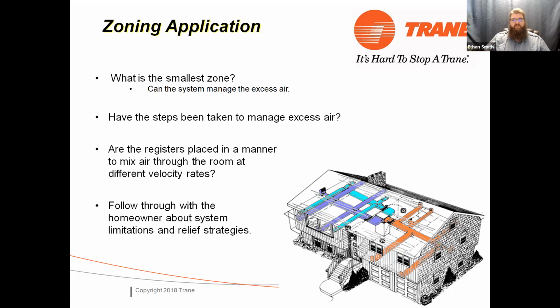I have a customer that I've been working with, a contractor, for upwards of 2 years, that thinks that because she sets her master bedroom to 65 degrees, she can then set her living room, which shares a wall with the master bedroom, to 75 degrees and have them be at set point all the time. Okay. Is that a realistic expectation out of a zoning system? No, not really. Maybe if that master bedroom was on a separate structure or had a 20-inch piece of insulation between it and the living room, we could get that kind of temperature gradient out of the zoning system.